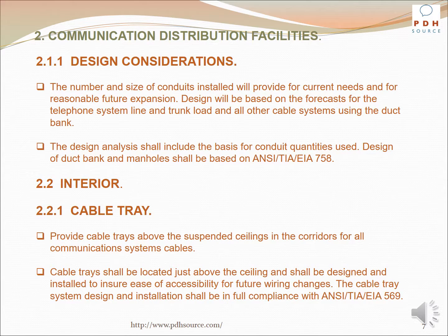The number and size of conduits installed will provide for current needs and for reasonable future expansion. Design will be based on the forecast for the telephone system line and trunk load and all other cable systems using the duct bank. The design analysis shall include the basis for conduit quantities used. Design of duct bank and manhole shall be based on ANSI 758.